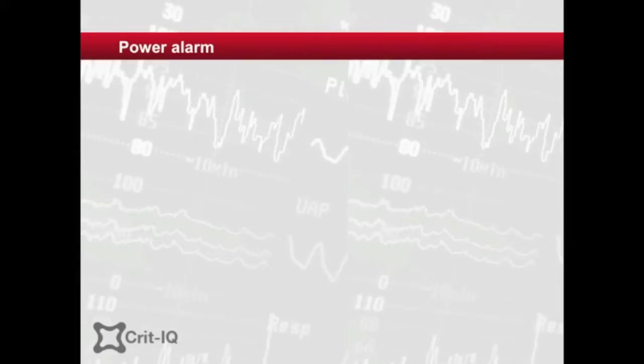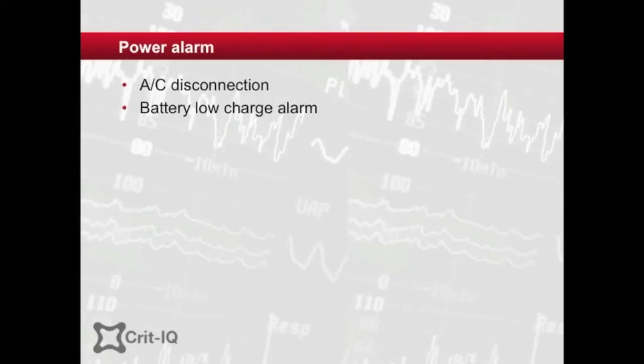Most ventilators will provide a visual, if not audible, alarm for disconnection from a power source. When on battery mode, they will also alarm when power is reduced to a potentially dangerous level. These alarms should be identified and dealt with promptly.